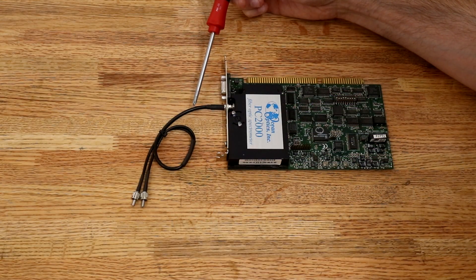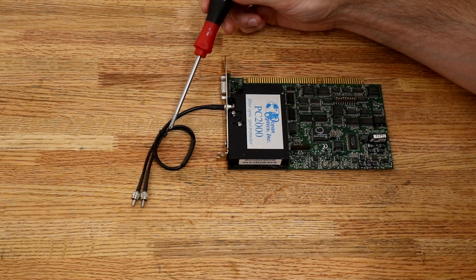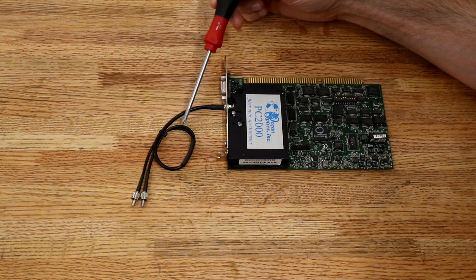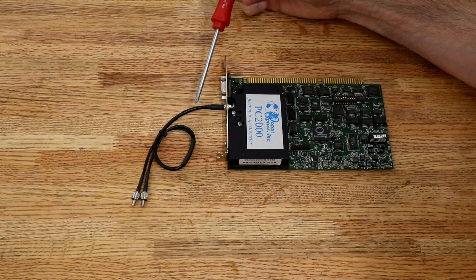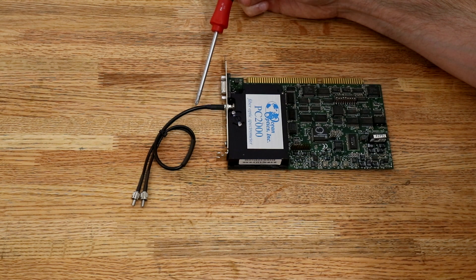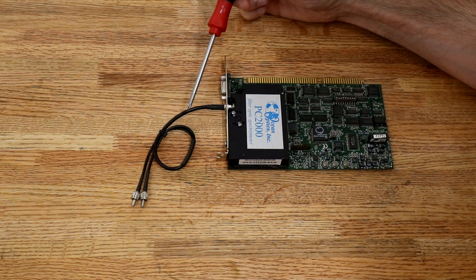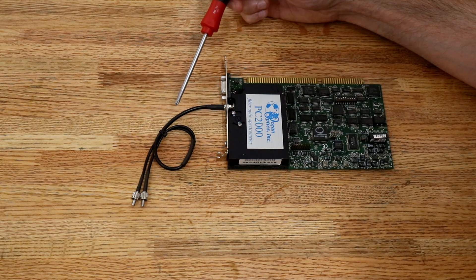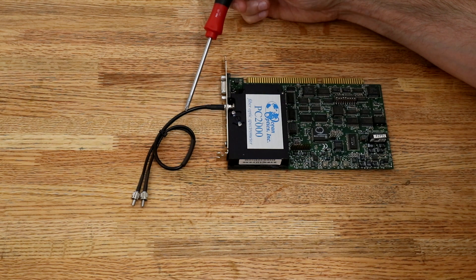Light is delivered to a spectrometer by a fiber cable. You have to be careful not to exceed the bend radius of the fiber cable, otherwise light may actually break through. The fiber cable is composed of two different types of glass: there's the core and the cladding, and that's surrounded by a jacket. The core and the cladding are slightly different glass with different refractive indices to help keep the light confined to the core.